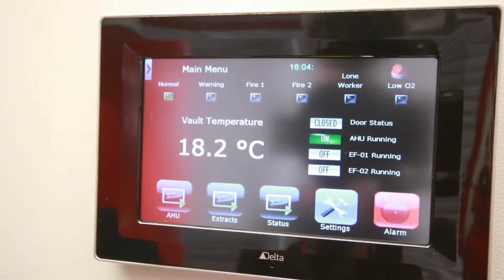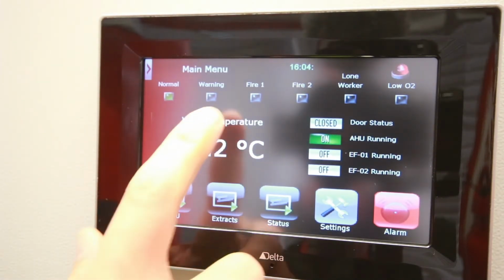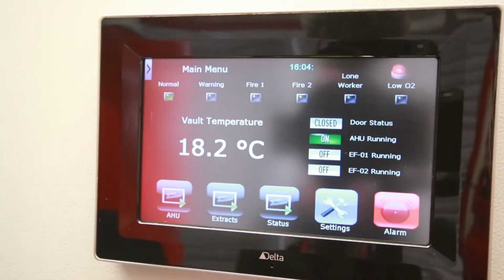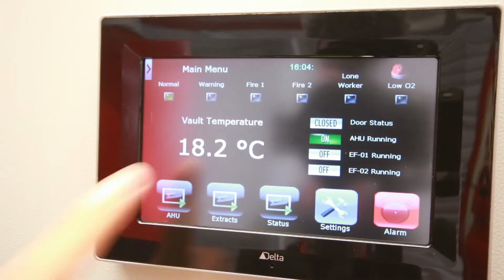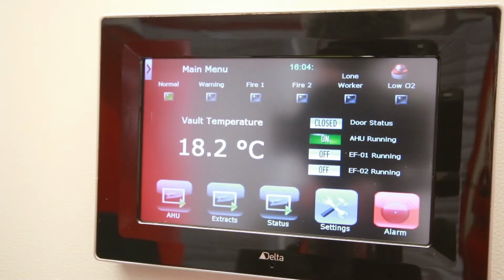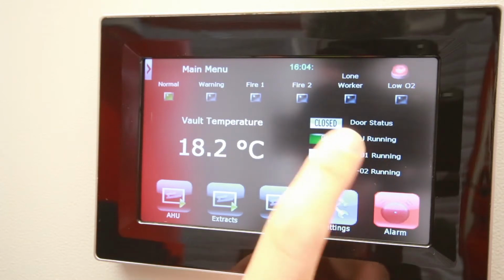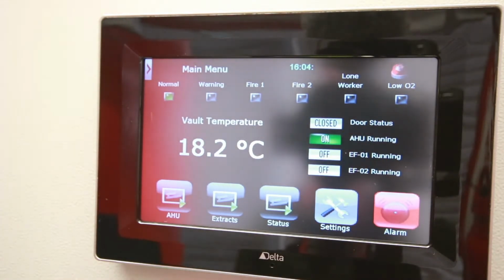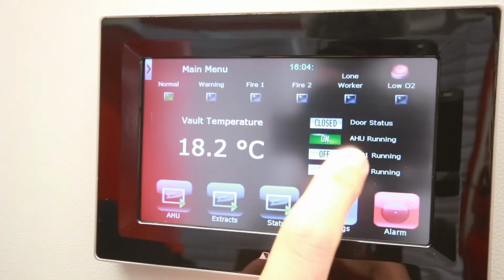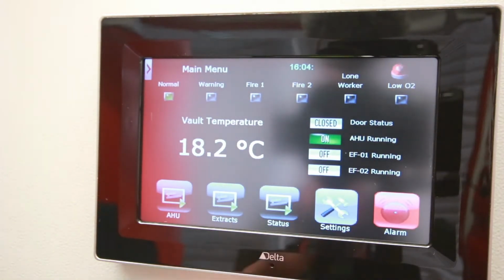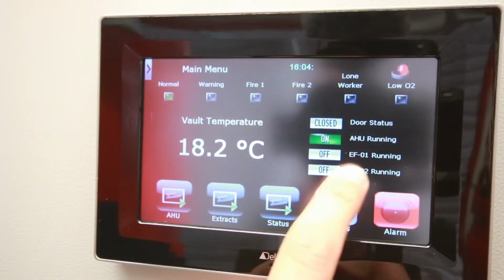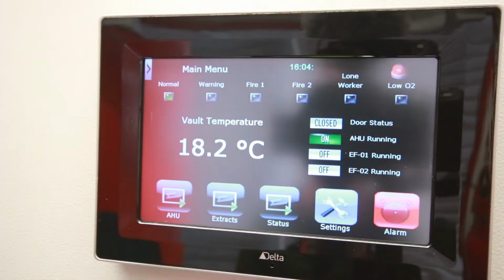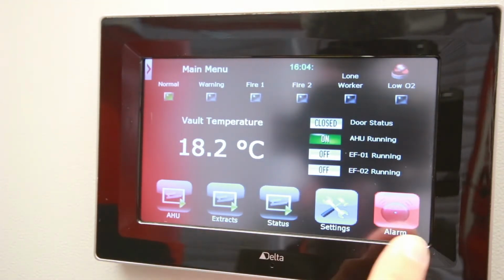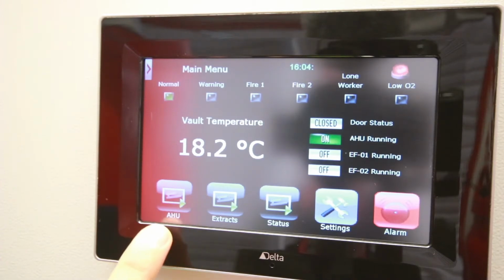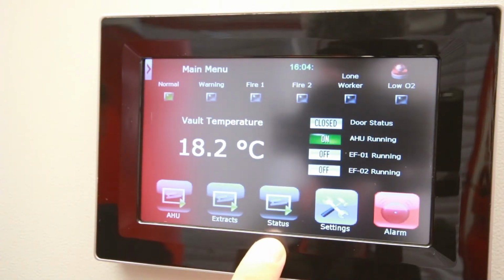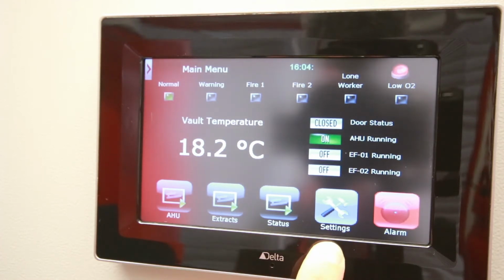Currently, as expected, we have a green light indicating everything is okay and no red lights on any of the other alarms. This is our internal Firevault temperature, currently running at 18.2 degrees Celsius. We have a door interlock alarm here, which is indicated as the door is closed, so operating correctly. We have our AHU running as normal, and our two extract fans, Extract Fan 1 and Extract Fan 2, in this case, are both off. At the bottom of the screen, we have shortcuts to the other main settings: our AHU controls, our extract controls, our status summary, advanced settings, and alarm log.